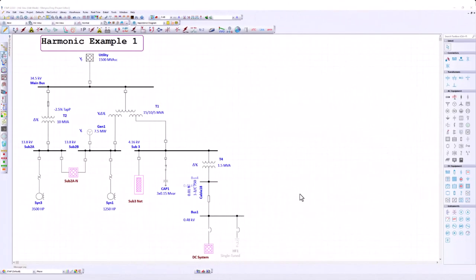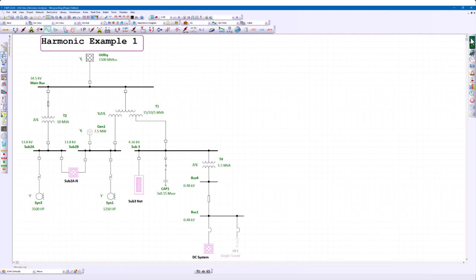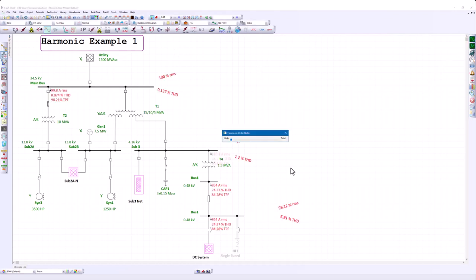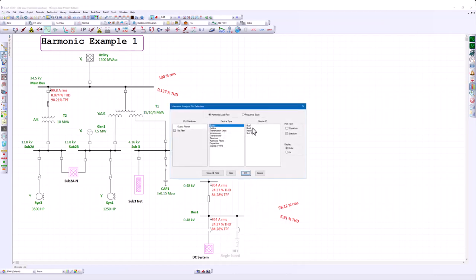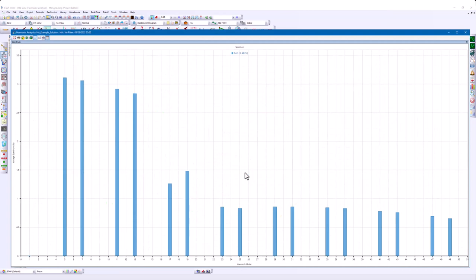Now let's take a look at how we are able to use the harmonic filter sizing feature to determine the size of my filter. First, let's start by running a harmonic load flow calculation. My focus would be at bus 1. Let's plot bus 1 and find out at which harmonic order, based on the spectrum, we get the highest harmonic distortion. Based on the plot, you can see that the fifth harmonic order generates the highest distortion. Okay, now we are going to eliminate the fifth order.